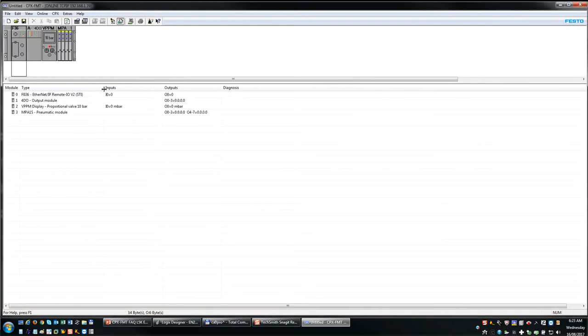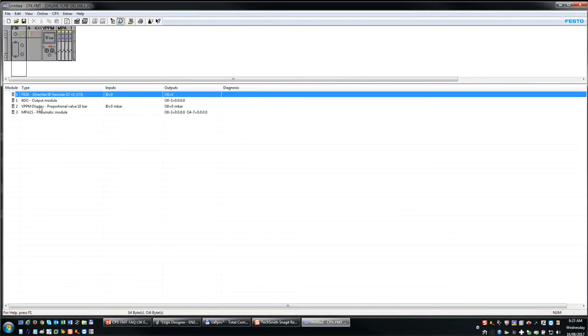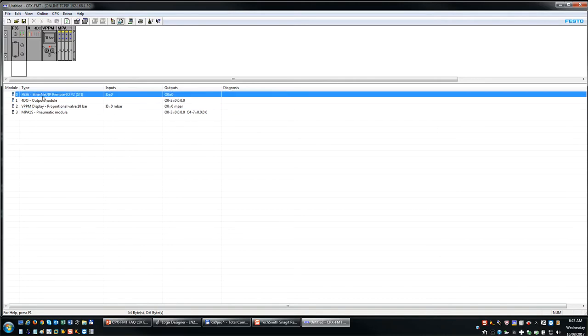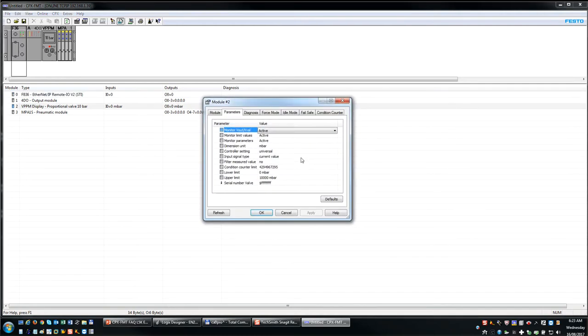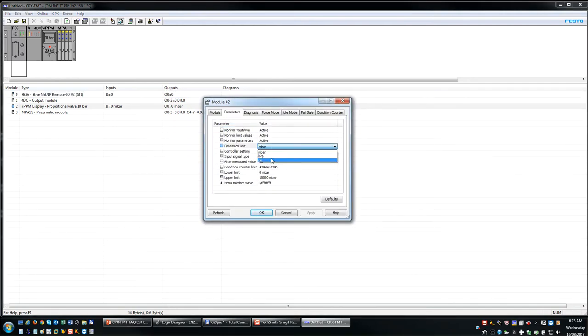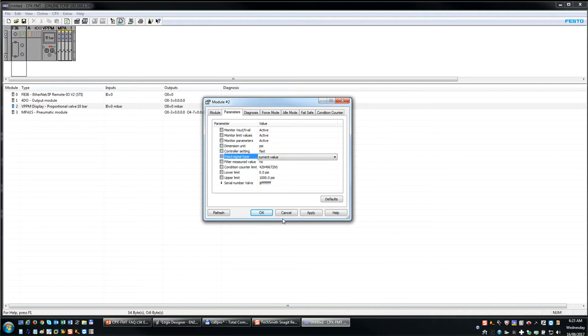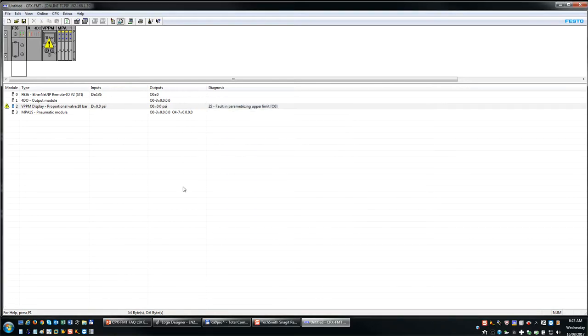Now it's going online. The first thing it does is it sucks up the information and all the configuration data. And at this point you're going to go and configure all your parameters. So this one here, I don't want millibar, I want PSI. I want a fast response time. And hit apply, hit OK.